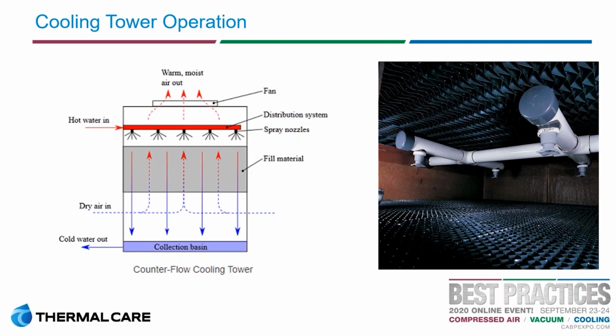And as long as we get a good spray pattern over that, we do a very good and effective job of getting that evaporation. If you look over to the left again at the diagram, that gray bar is what we're representing as the fill. The warm water is sprayed over that. Then we have a fan at the top of the unit, and what it does is pull in the air from the sides at the bottom and then up through the tower across that fill. And that fill is now covered in water.